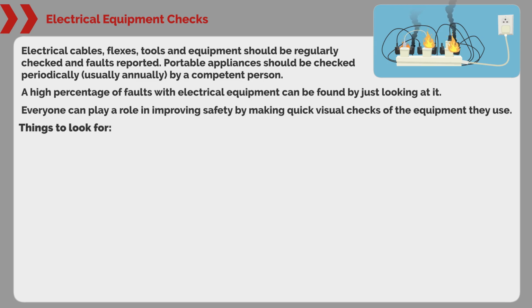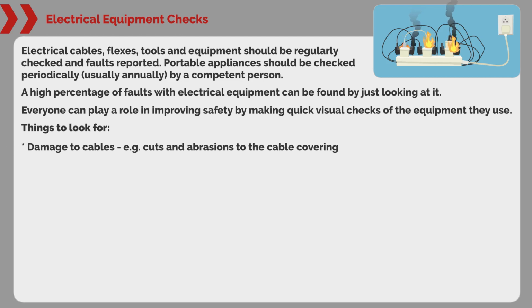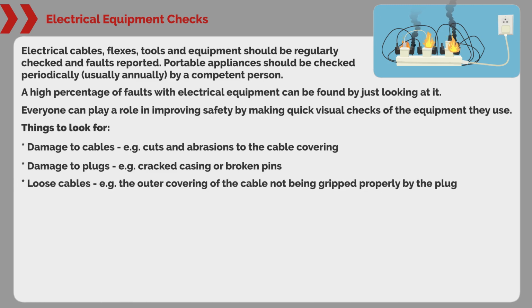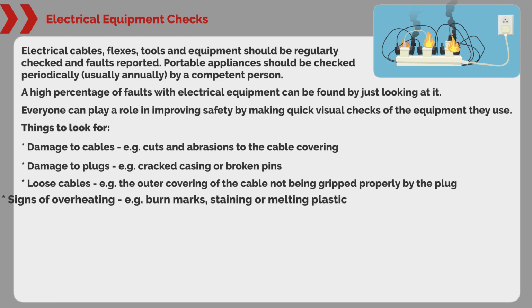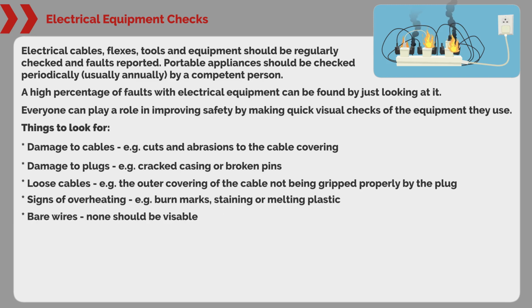Things to look for. Damage to cables, for example cuts and abrasions to the cable covering. Damage to plugs, for example cracked casing or broken pins. Loose cables, for example the outer covering of the cable not being gripped properly by the plug. Signs of overheating, for example burn marks, staining or melted plastic. Bare wires, none should be visible.